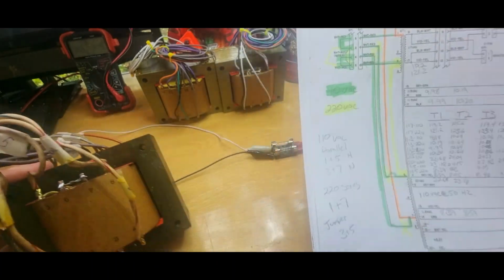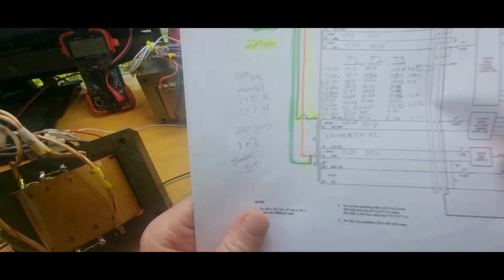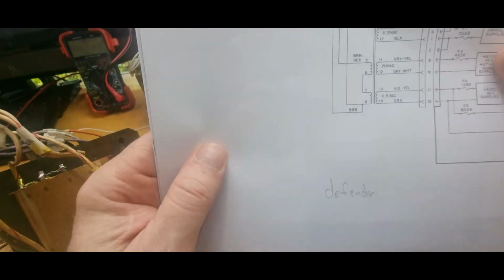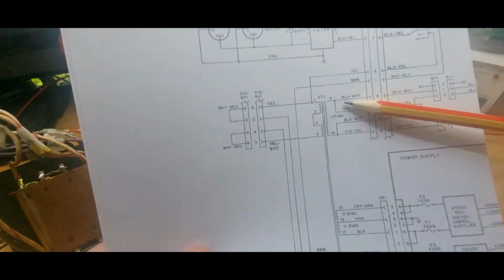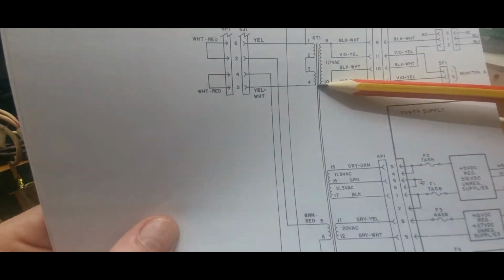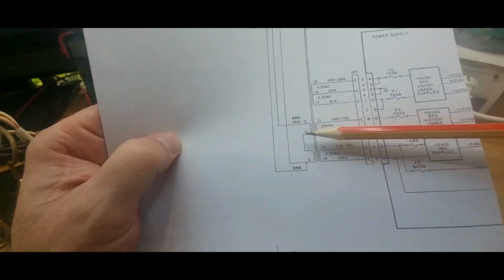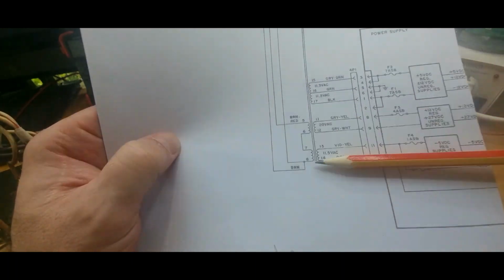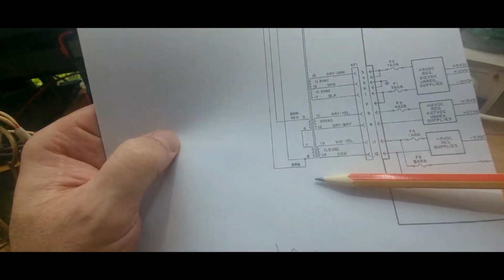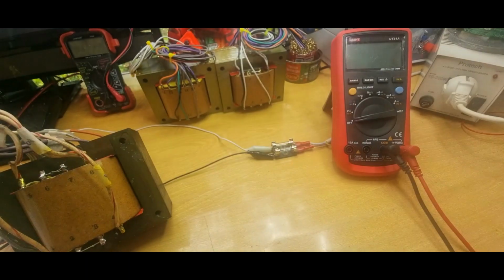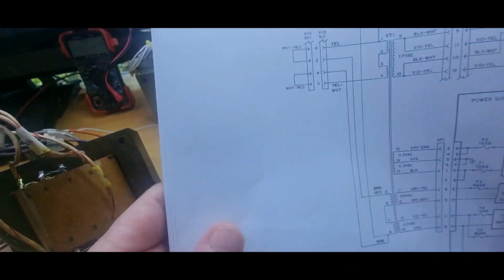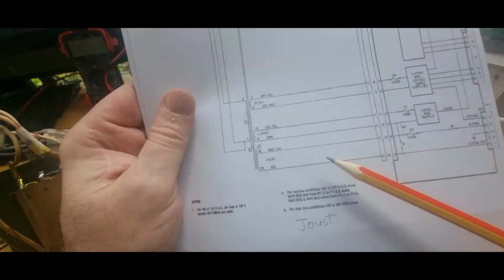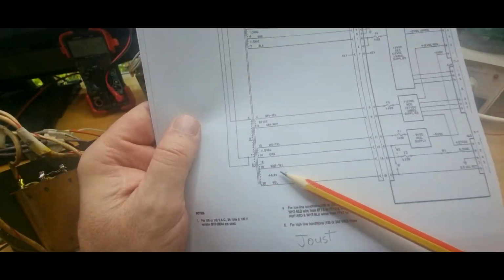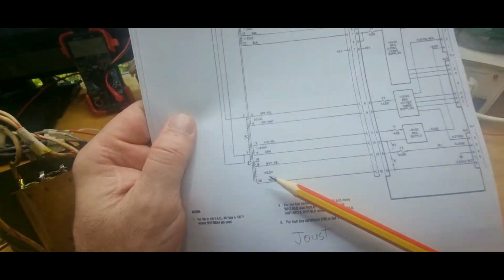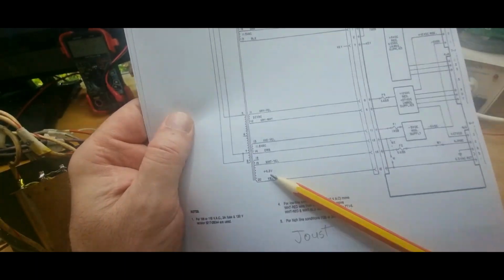Going through the drawings again — they're very similar, so be careful. This is our Defender drawing: we have 4 taps on the primary side for one winding, and no additional winding, which matches the tap situation on our transformer. Now here's the Joust drawing, similar to the one I'm working from but not marked up — it has an additional winding on the secondary side for 6.3 volts.